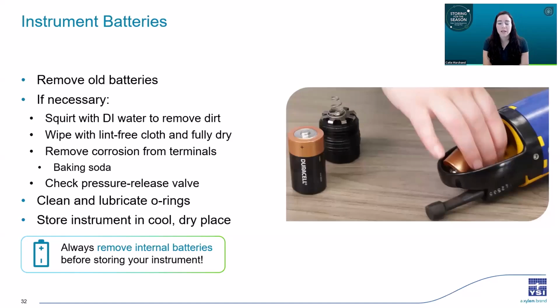Also, if your instrument has an internal battery compartment, it will likely have a pressure relief valve. That's for safety purposes in case the battery off-gasses. So inspect the valve to see if it's popped up. On the EXO 2 and 3, it's here in the battery cap. If it is, you might need to push it back in before you put it back in your instrument.